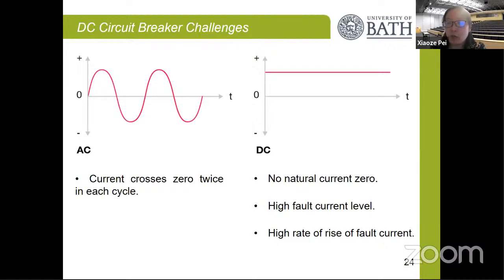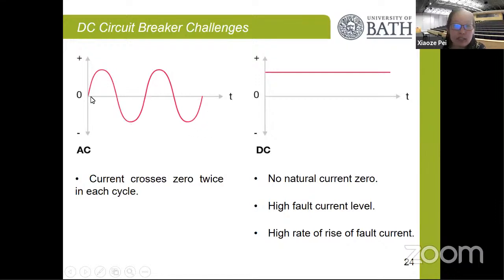So now let's talk about what the challenge is. Why do we look into the DC circuit breaker? We know this is an emerging area, going to have more and more DC. So what is the challenge? In an AC network, the current and the voltage cross zero twice in a cycle. So if we have a mechanical switch, we can interrupt with it, and this current zero crossing helps to extinguish the arc in the mechanical switch. But what happens with DC? With DC, there is no natural current zero, so the mechanical switch is not able to extinguish the arc. And secondly, in particular for the onboard system, because everything is quite closely coupled together, there are even higher fault current levels and also a very high rate of rise of fault current.